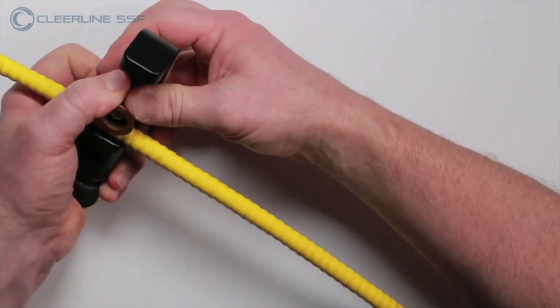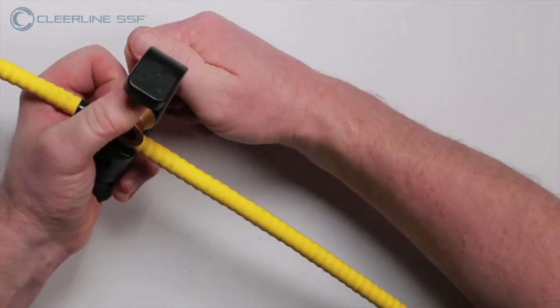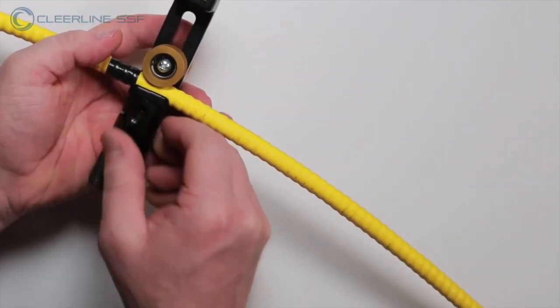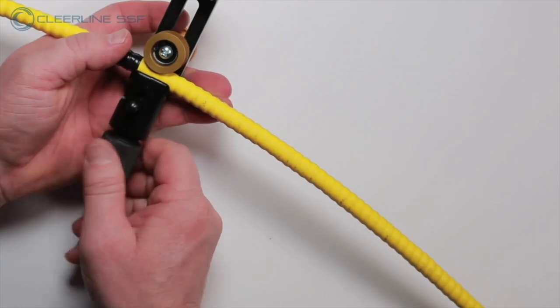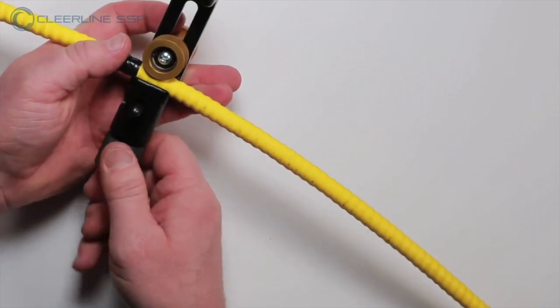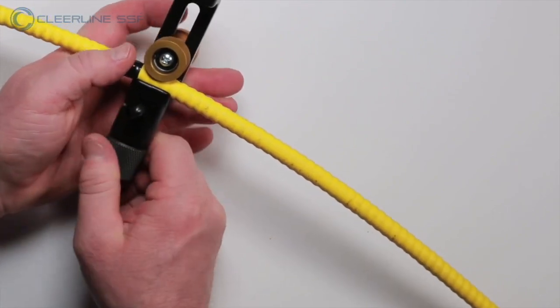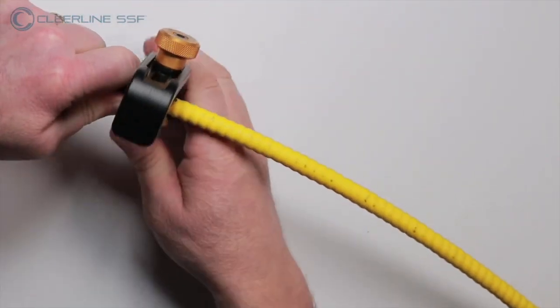Lower and hold the rotating wheel firmly against the cable, then tighten the gold side screw. Tighten the base thumb screw until firm but not completely tightened. Now rotate the tool around the cable, tighten the base thumb screw, and repeat as needed until the base thumb screw is fully tightened.